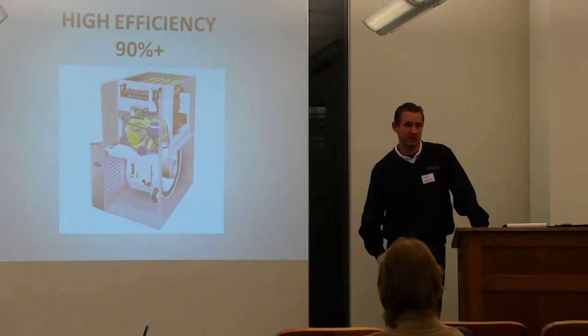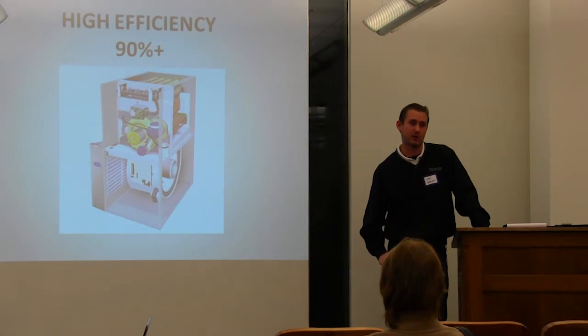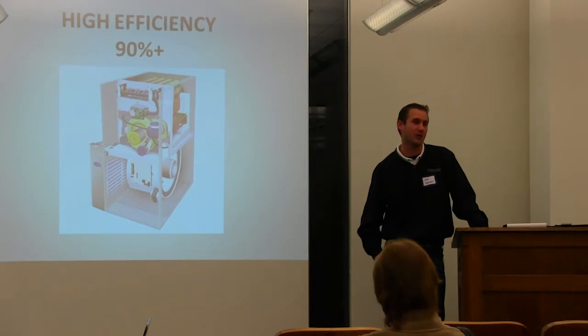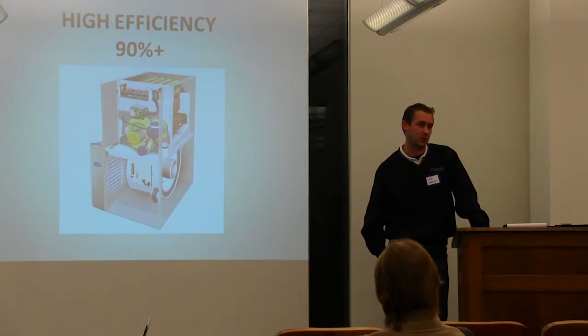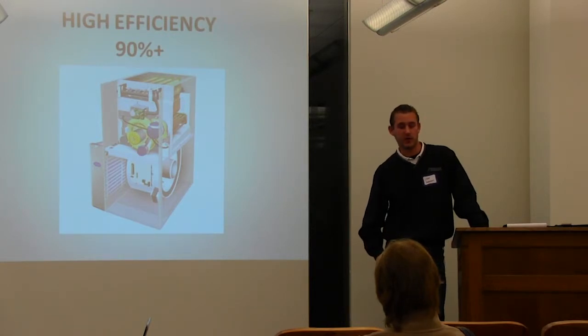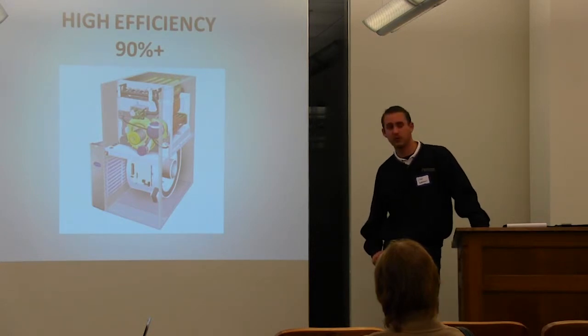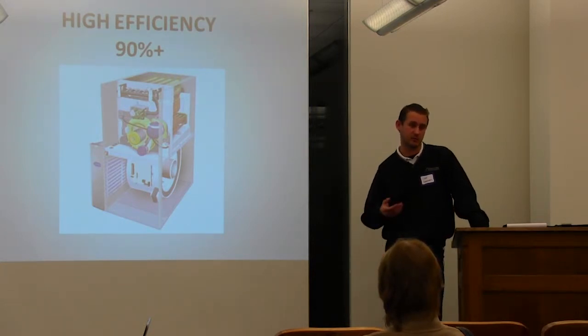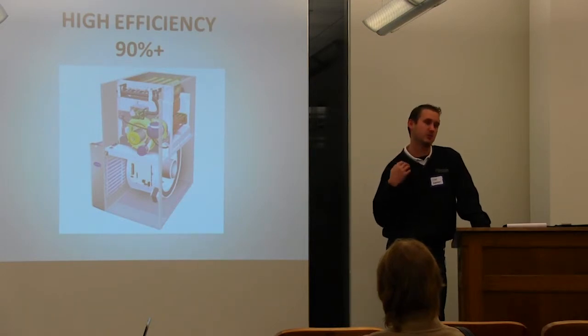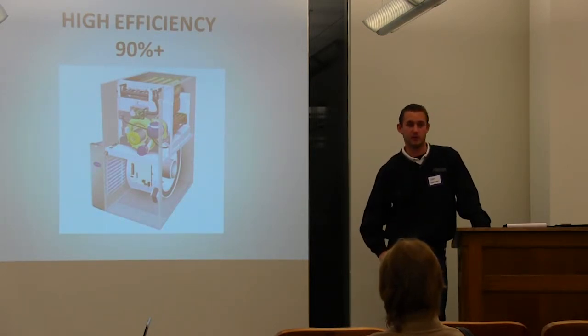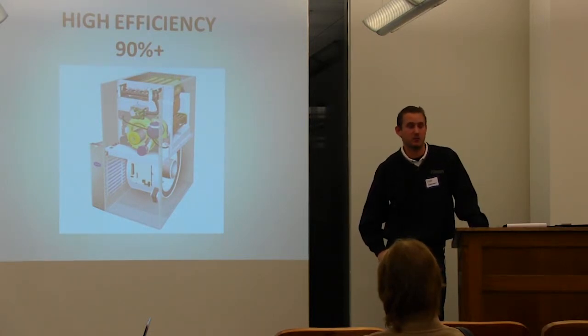So those vanes have a tendency to collect dust and dirt, especially if your filter's been out for any amount of time. If you're a subsequent homeowner, you have no idea how well the previous homeowners stayed up to date on their filter changes, or if they used a filter at all. And if you have no filter to pull the dust out of the air, you'll have a big tendency to accumulate all that dust and dirt on the vanes. And once those vanes plug up, it's not grabbing the air and pushing it through your furnace anymore. So your blower is just going to run and run and run, and you're not pushing any air. So your efficiency is drastically reduced.